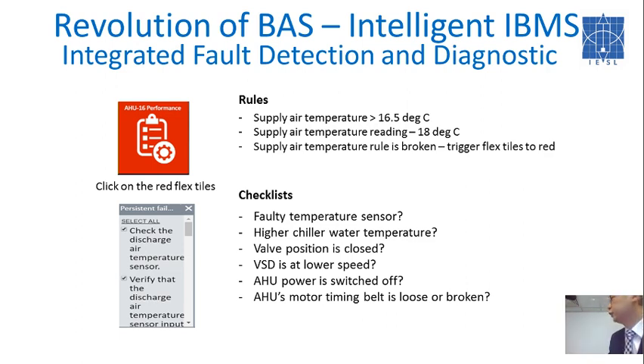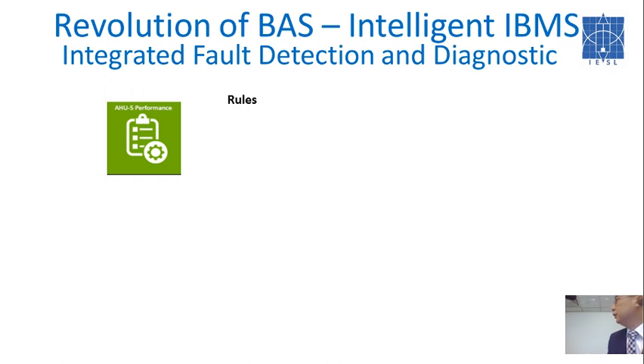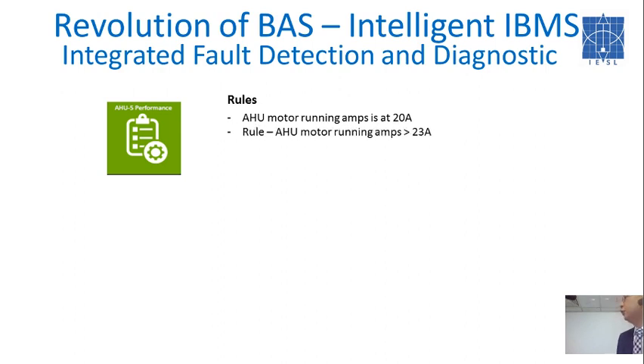Right. So I have another checklist itself. Is the AHU filter dirty? It blocks the airflow itself. That's why the supply air temperature increases. So I have another IFDD rule. Let's say you have power meters on your AHUs monitoring the running amps, and normal condition is running at 20 amps. I can set a rule that if the AHU's running amp is greater than 23 amperes, you create a fault or a warning itself. It's not a fault, it's a warning.